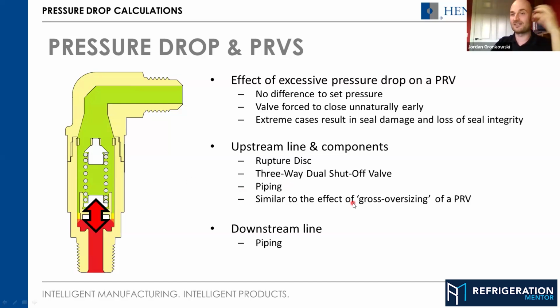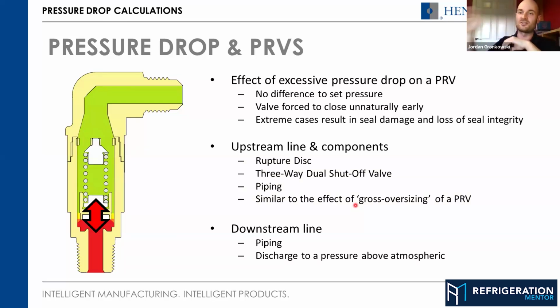That's usually caused by excessive piping, either length or too small a diameter. It can also be caused, not so much for CO2, but for some refrigerants and things like ammonia, where we discharge into a vessel rather than into the atmosphere. That can obviously have a back pressure effect as well. You get superimposed back pressure. And that's an important point: all conventional valves are back pressure dependent. They are designed to, and must, relieve to atmospheric pressure. You get some PRVs that are specifically designed to be back pressure independent. They can deal with a certain level of superimposed back pressure, as they call it. So they're discharging into a pressurized environment as opposed to discharging to the atmosphere. So it's important to make sure you get the right valve for the job.